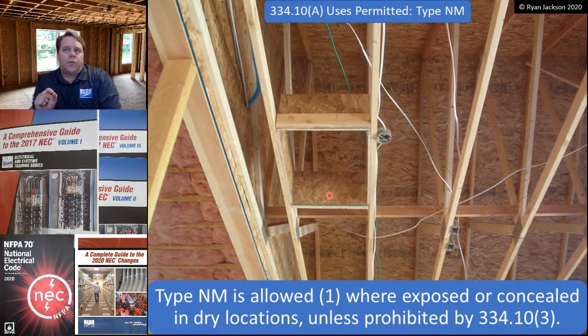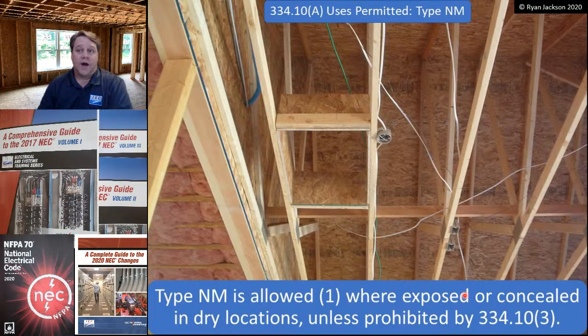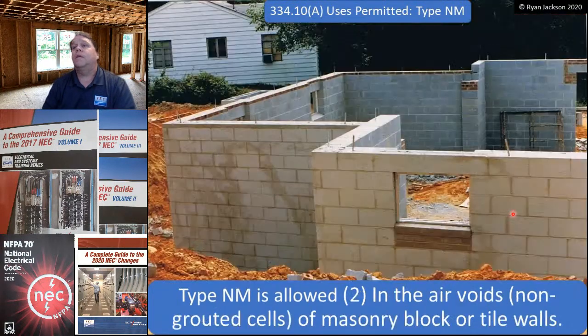Okay, 334.10(A), uses permitted specifically for type NM. You see, 334.10 that we just read is for type NM and NMC. These two items are specific to type NM, not NMC. Type NM is allowed where exposed or concealed in dry locations unless prohibited by type of construction. Okay, so yeah, it can be exposed or it can be concealed, but in commercial buildings, of course, it has to be concealed. NM cable is also allowed, number two, in the air voids of masonry block or tile walls.